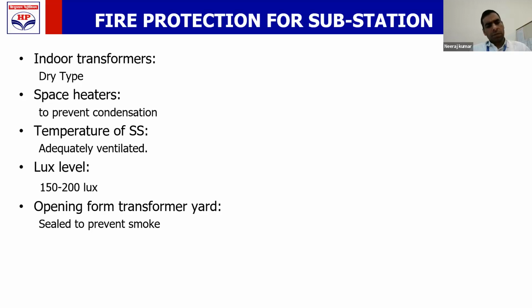Space heaters. Vizag refinery or some other installations long time back has seen an issue that water started condensing inside the panels. Why did it happen? The weather is cold, humidity is very high, the panel is not in running condition, it is in off condition, and the space heater is not there. So what happened? Water condensed inside the substation and the panel. And when you switch on that panel, your dielectric strength is gone, and there could be a chance of explosion or fire.